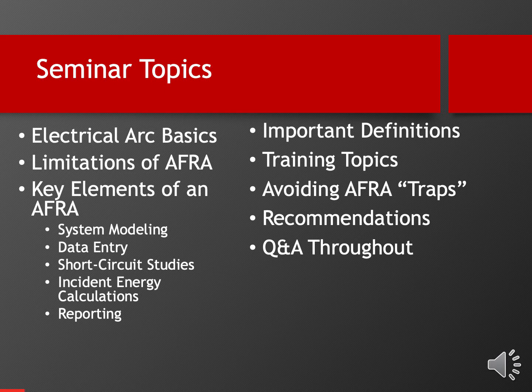And again, we're going to begin with a discussion of what we know about electrical arcs, in particular how that information is useful in developing protective systems for workers who are exposed to electrical arc hazards. I want to talk about the limitations of an arc flash risk assessment study. There's a lot of things the study does well. There's a few things the study does not do at all, and we want to make sure and cover that so they're properly integrated into the protective systems associated with the study. We'll talk about the various elements of the arc flash risk assessment study, ranging from the system modeling to the short circuit studies, ultimately with the incident energy calculations, and probably most importantly, the reporting element.